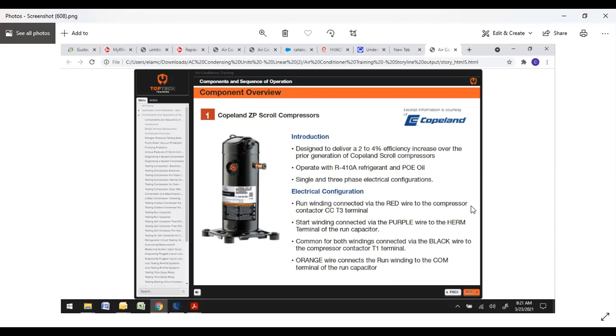Now, if you cross these up in the right combination, I get this quite often. Guys just start putting things back together, or somebody else does it and doesn't pay attention. If you miswire these, what you will get is what looks like a locked rotor compressor. Electrically, the amp draw will look just like a locked rotor compressor.